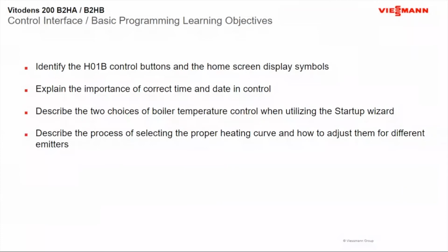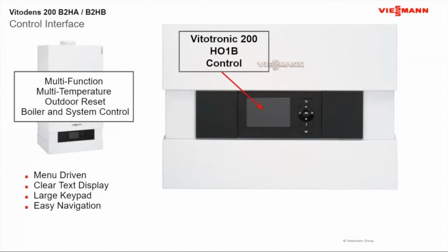On this one here, we're going to go over your HO1B, which is that interface that you're looking at in the front of the control. The symbols, what they mean. I always like to go over the importance of the time and date with this control. As well as we'll talk about the startup wizard and temperatures, either doing a mix or a fixed set point. And how our heating curves work and where you might want to start adjusting them. All right, so let's get started. So that is the HO1B interface control. And if you've done multiple boilers, this used to be our cascade control interface as well. Now that has turned into more of a touch screen. So if you're doing multiple boilers, you'll see a different image than this touch screen here.